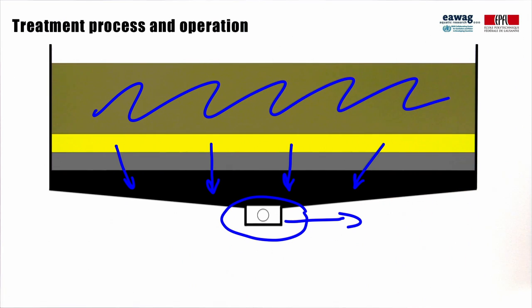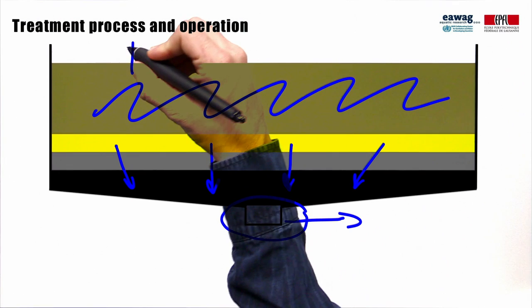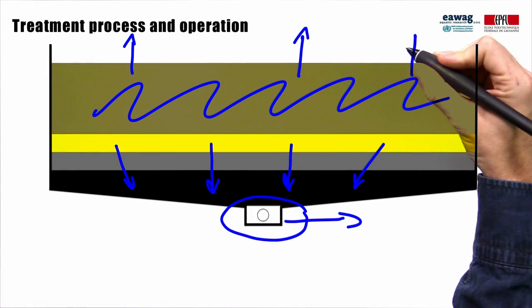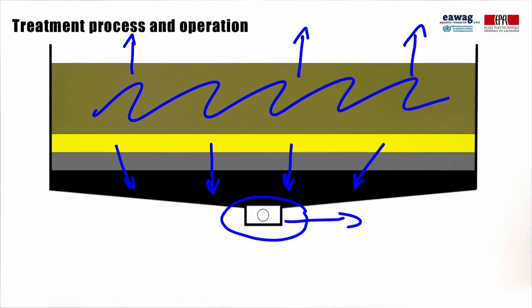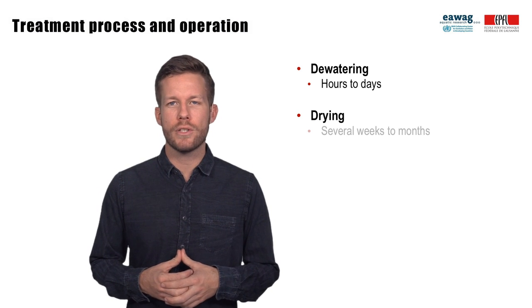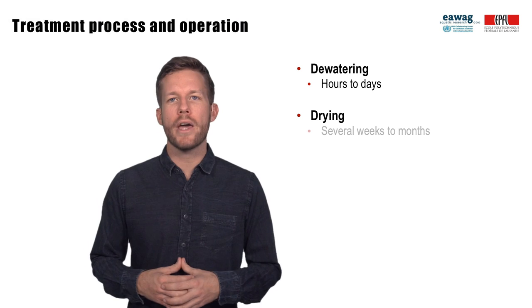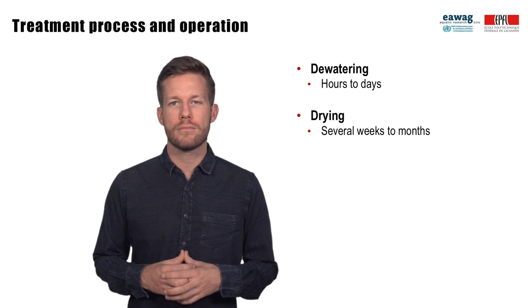The sludge accumulates on top of the sand filter layer. Following dewatering, during drying, liquids and solids are further separated by evaporation. Dewatering usually takes several hours to days, whereas the duration of drying is usually longer and takes several weeks to months.